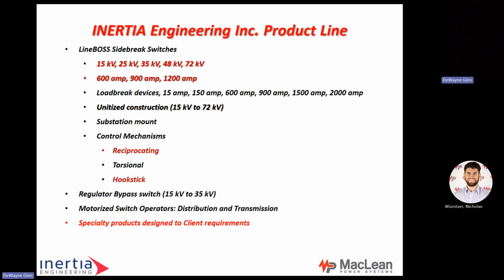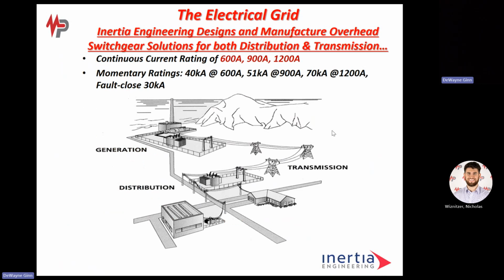Basically, we say there's 1.9 million different configurations in the switch world with our switches, so we can try to help that customer develop whatever they need. This is where we play, from generation and transmission all the way to distribution. Basically, our continuous current ratings are 600, 900, 1200 amps. Momentaries, 40 kA at 600, 51 kA at 900, 70 kA at 1200, with a fault close of 30 kA.